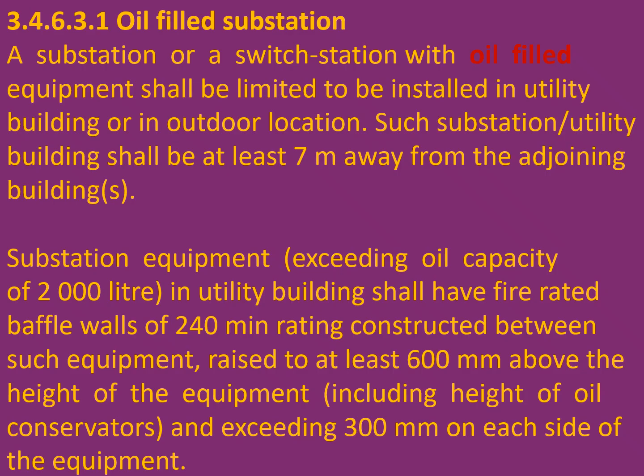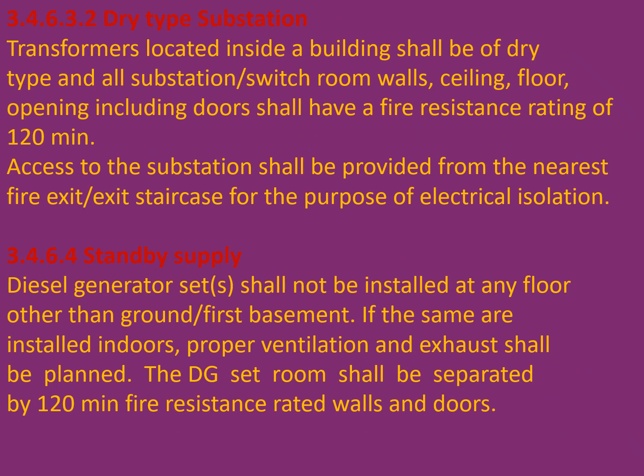Constructed between such equipment, raised to at least 600 mm above the height of the equipment, including the height of oil conservator in case of transformers, and exceeding 300 mm on each side of the equipment. Friends, in case of dry type substation, transformers located inside a building shall be of dry type and all substation or switch room wall, ceiling, floor opening, including door shall have a fire resistance rating of 120 minutes, that means 2 hours. Access to substation shall be provided from the nearest fire exit staircase for the purpose of electrical isolation.